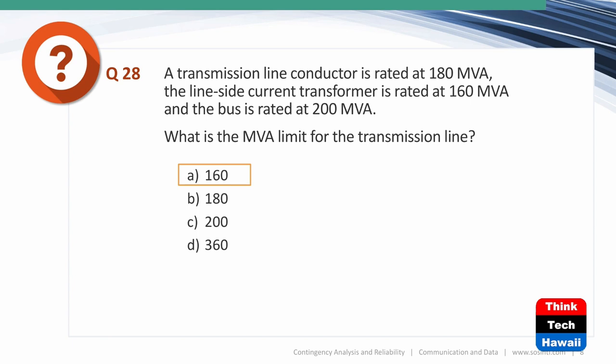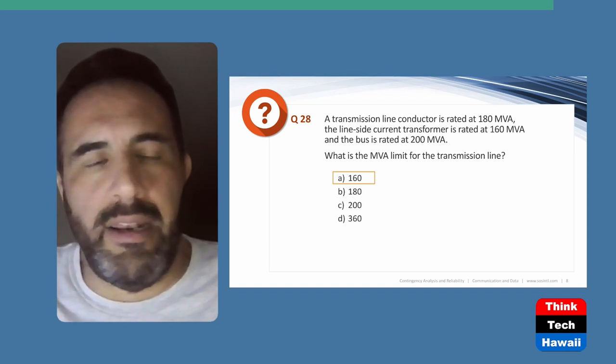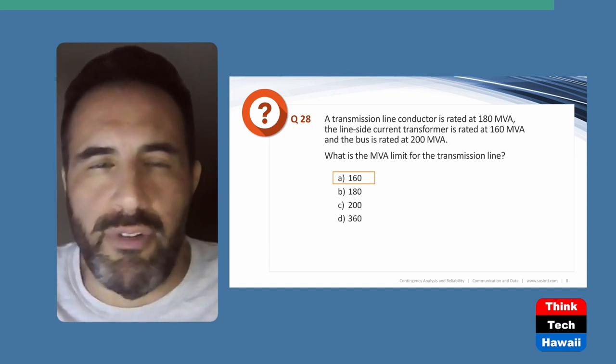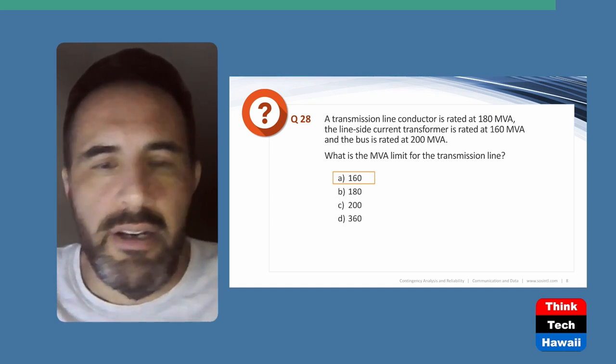Final question: A transmission line conductor is rated at 180 MVA. The line-side current transformer is rated at 160 MVA. The bus is rated at 200 MVA. What is the MVA limit of the transmission line? The answer is 160 — the weakest link — the lowest-rated element in that set of components is the line-side current transformer.